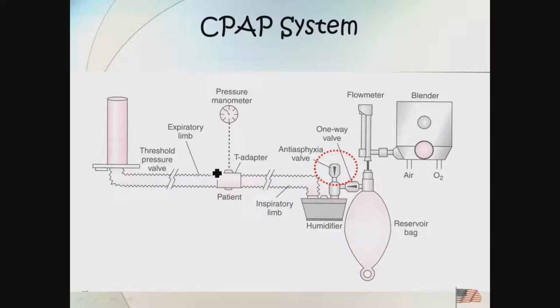Okay. So the purpose of the anti-asphyxia valve is to allow them to access atmospheric air should the system fail for some reason or other. Going through my inspiratory limb to my patient, they are able to breathe in and out through there. I have a pressure manometer monitoring what the pressure is at that point. So as they draw gas in, you're going to see a drop in airway pressure, just like you would expect to see on a CPAP breath. Then as they exhale back out again, there's a small positive pressure that is created, and you have, in essence, a sinusoidal waveform that's elevated to a higher baseline.